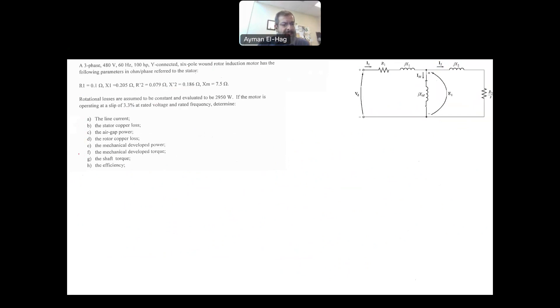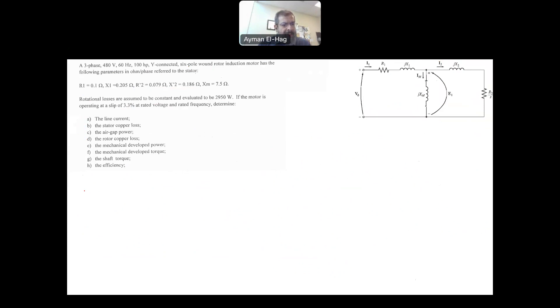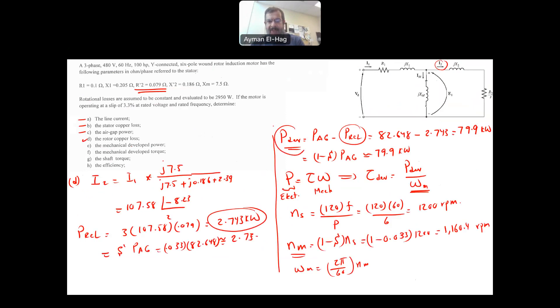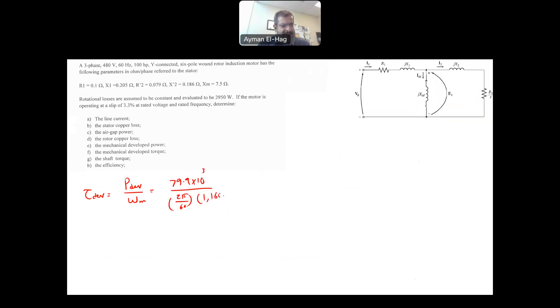Now we can find the developed torque. Torque_developed = P_developed / omega_M = 79,900 / (2π/60 × 1160.4) = 657.5 Newton meters. So we have found both the mechanical developed power and the mechanical developed torque, which are related to each other.